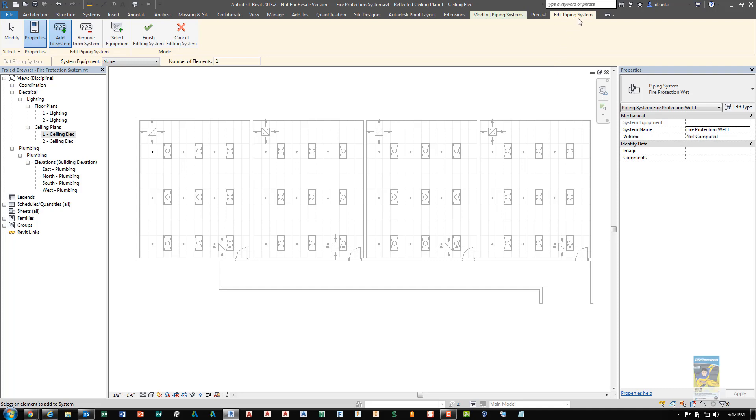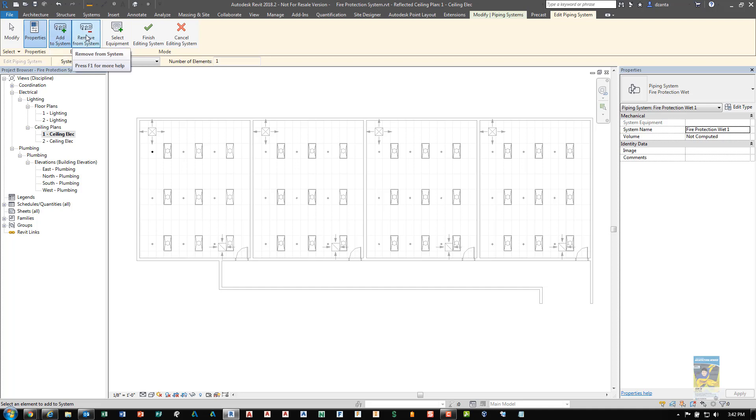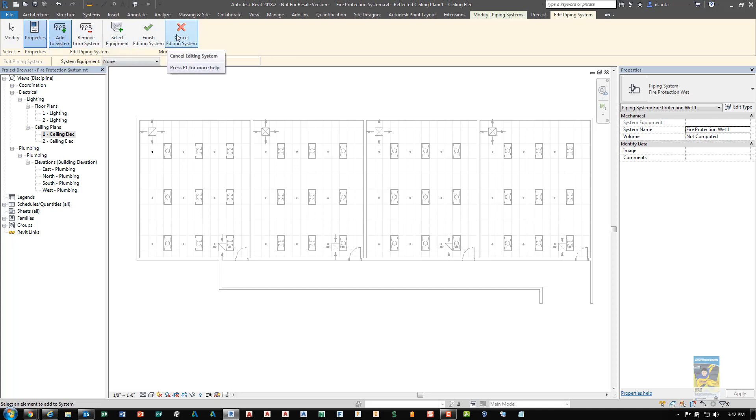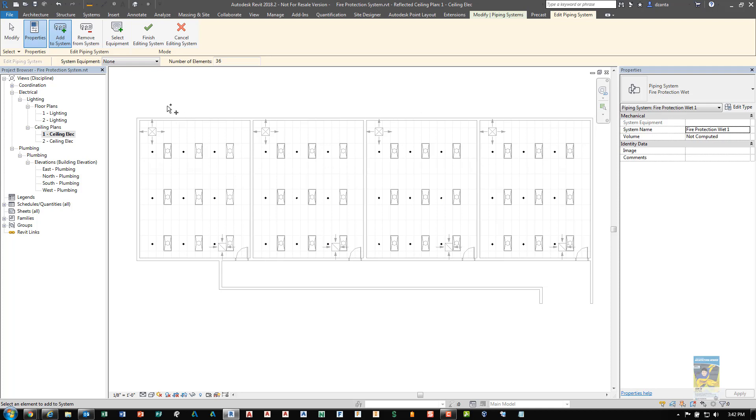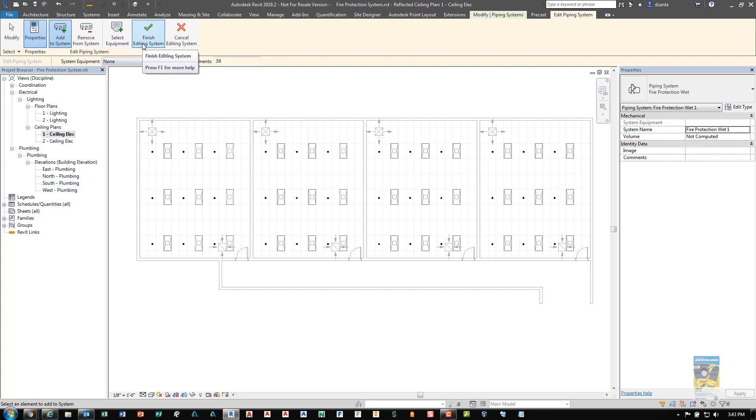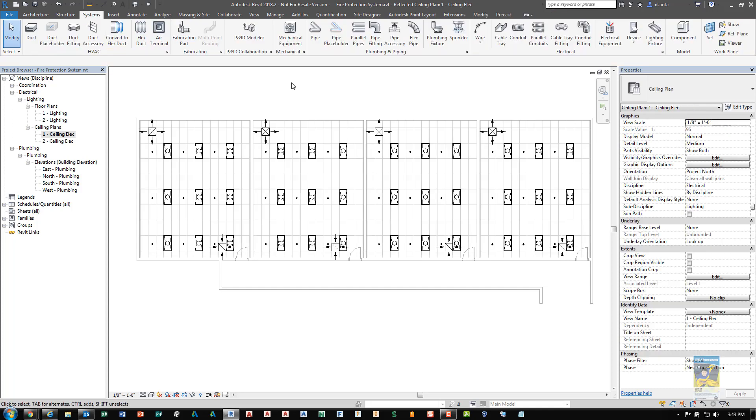And you'll get a pinkish skin tone colored contextual tab in the ribbon called edit piping system. And in here you have add to system, remove from system, and select equipment. And then finish and cancel. By default, add to system is highlighted. So it's asking you to pick all the other sprinkler heads that belong to the system. So I'll just choose all of them. If I have a specific piece of equipment that I want to use in the family to tie to this system, I can choose select equipment and touch it. Or I can pull it from this drop down list. I don't have any. So it's not going to give me a list. I'll click finish for now. And the third step is finished. So we have told the software these objects are part of a system.